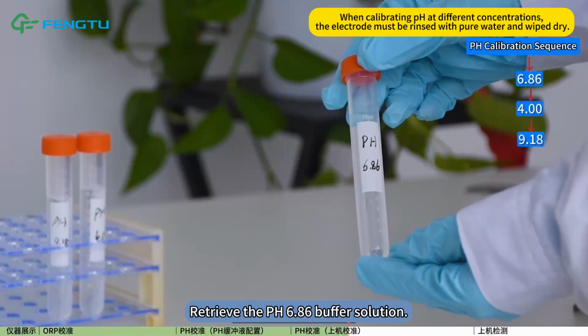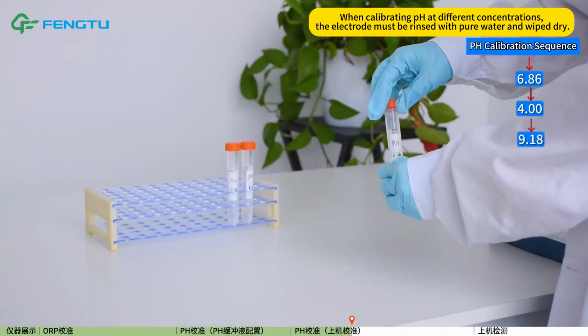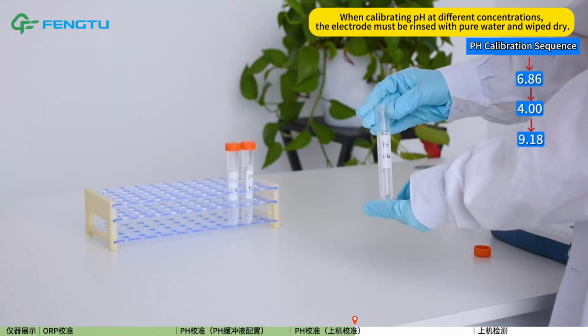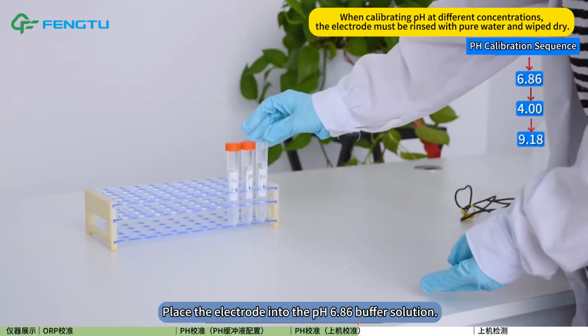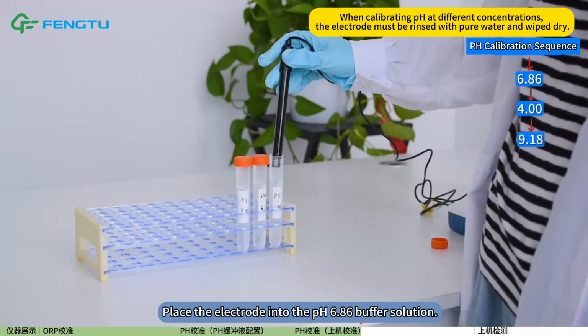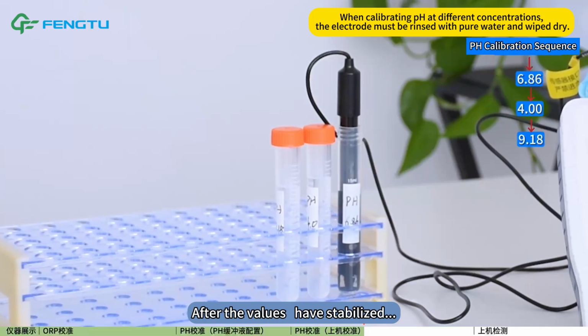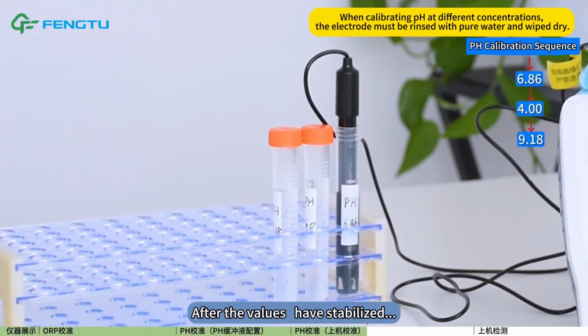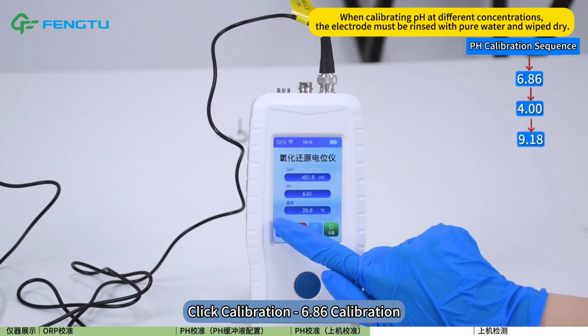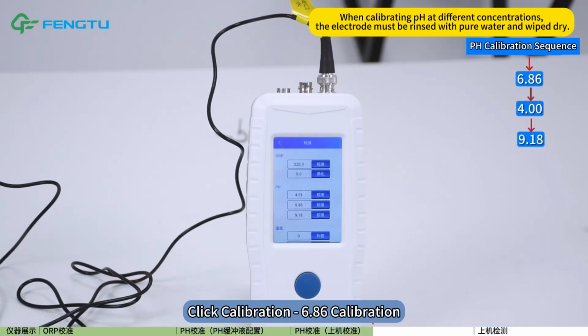Retrieve the pH 6.86 buffer solution. Place the electrode into the pH 6.86 buffer solution. After the values have stabilized, click Calibration 6.86 calibration.